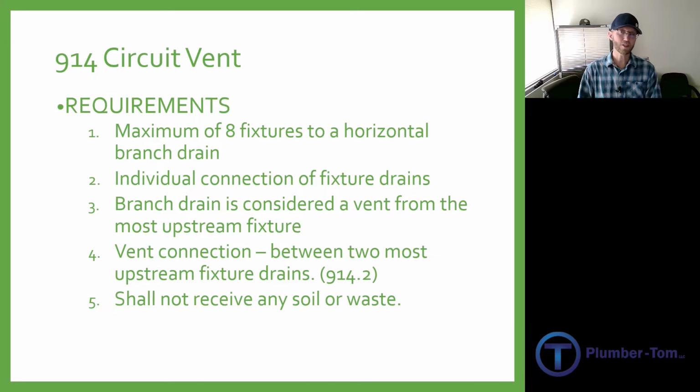That has to come between the 2 most upstream fixtures in this horizontal branch. And once again, that vent is not allowed to have any soil or waste coming into it. It's completely a dry vent.